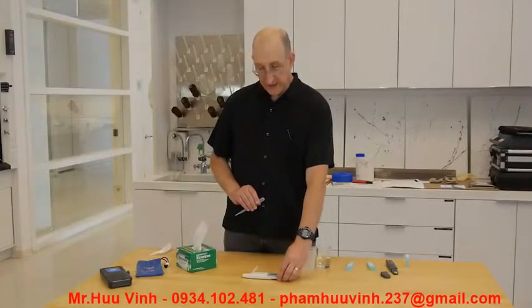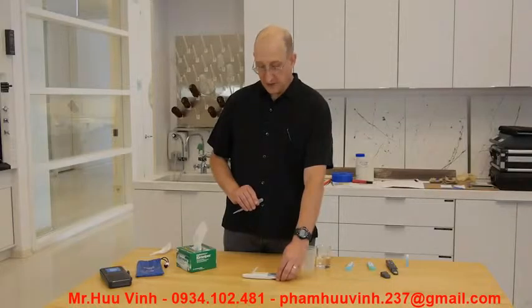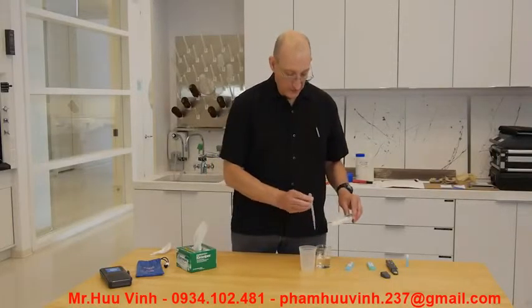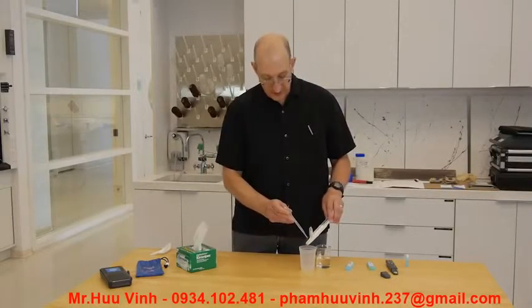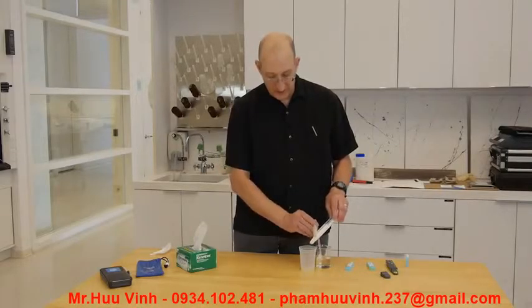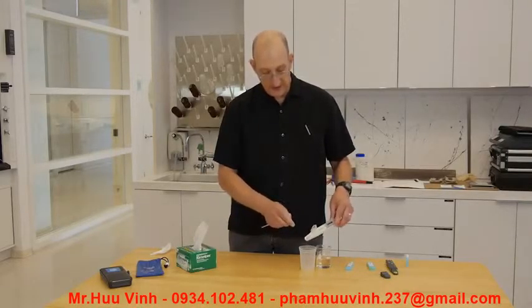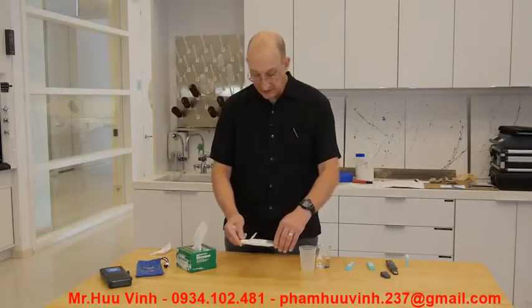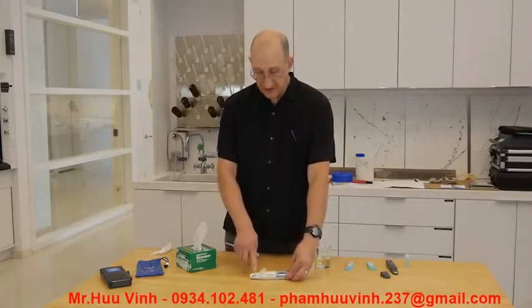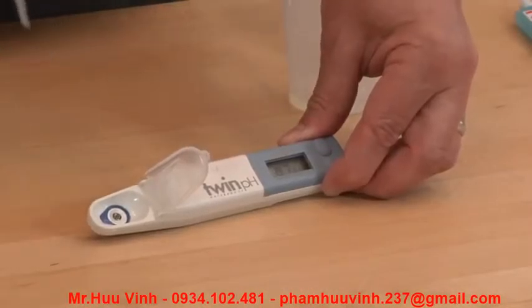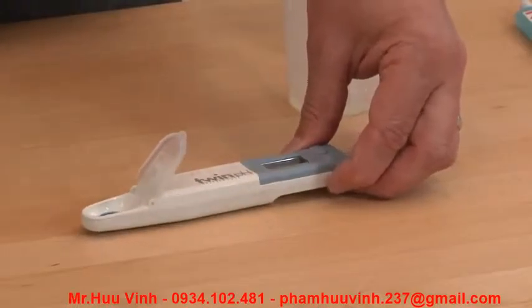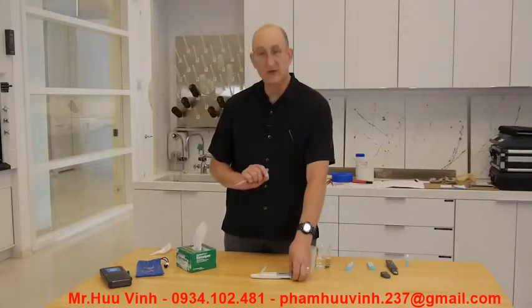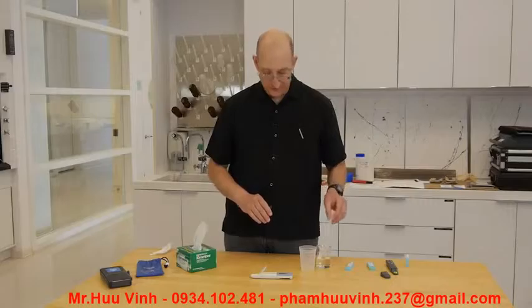When we've got our calibration at pH 7 finished, we want to rinse the sample well. Because we're measuring pH, it is not so concentration dependent, so we don't really have to blot the inside of the meter. If we do blot it, the glass membrane over the measuring electrode is very sensitive, so you really want to be very gentle, which is why I generally don't blot the electrode.